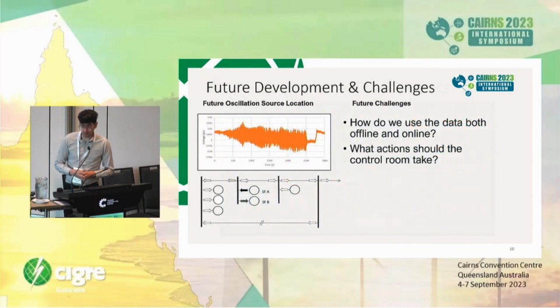So this is one of the applications that we've been looking at. Looking at oscillations, as we mentioned, for those system strength issues. We've got a tool in place at the moment that's monitoring oscillations in the system up to about 25 hertz. Our tool has been able to use PMU data to capture those kinds of oscillations and alert us in real time when something like that is happening, and it's been very highly successful since we've been implementing it.